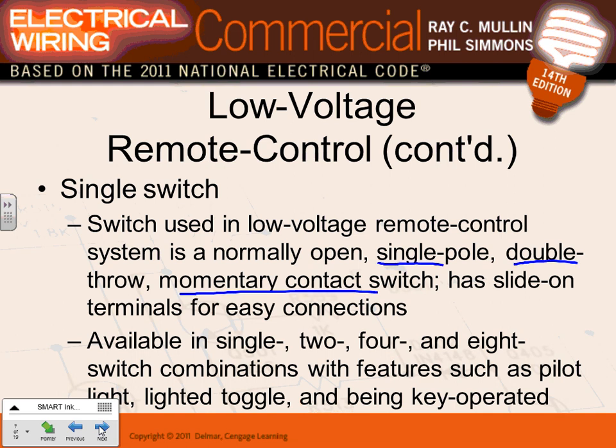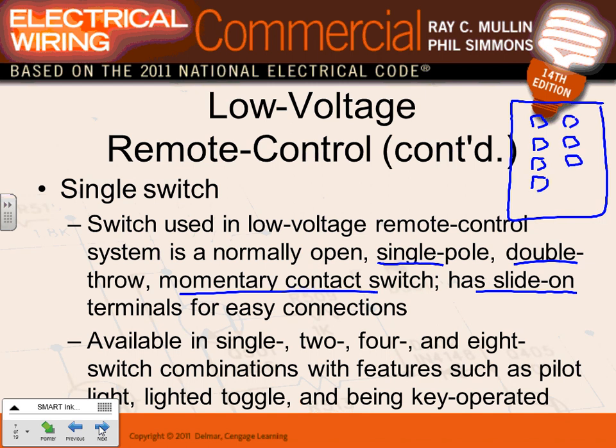Okay, switching. So when it comes to switching, guys, you can have single pole, you can have double pole, momentary contact, all of them are momentary contact, with slide on terminals for connections, available in single, 2, 4, or 8 switch combinations. Here's the fun thing about these: I can have a box like this, and inside that box I can fit tiny little switches like this, guys, 8 low voltage, these are 8 channel. Here's my 8 switches right into a single gang box. You can fit 8 switches in a single gang box.